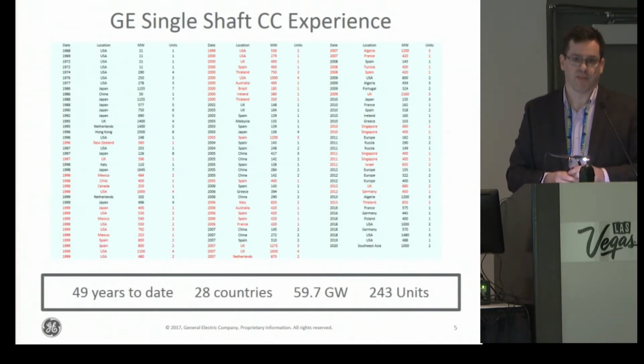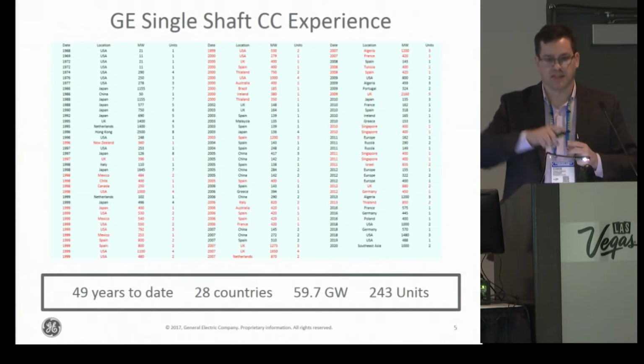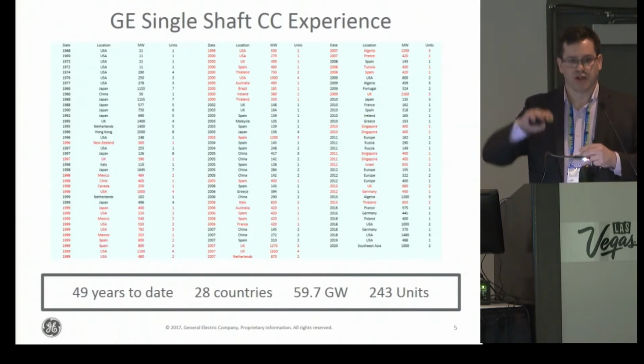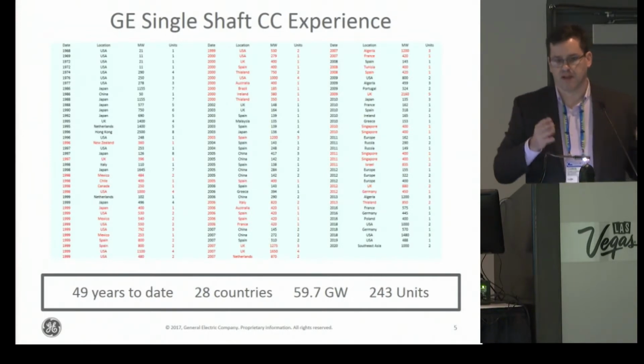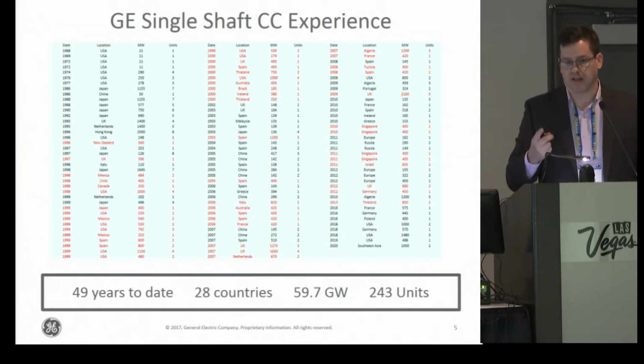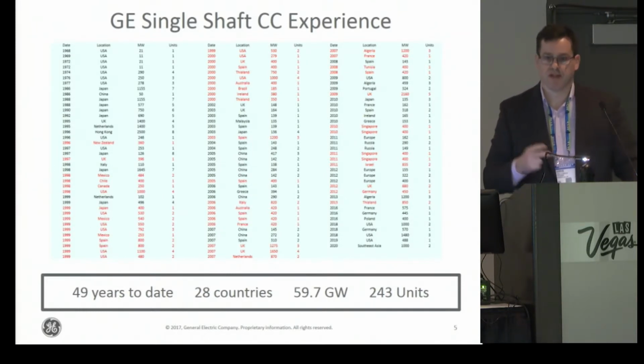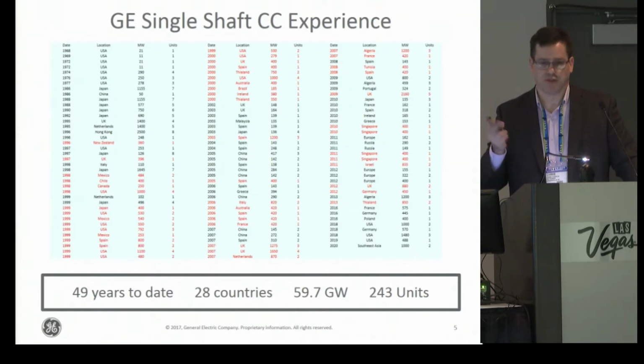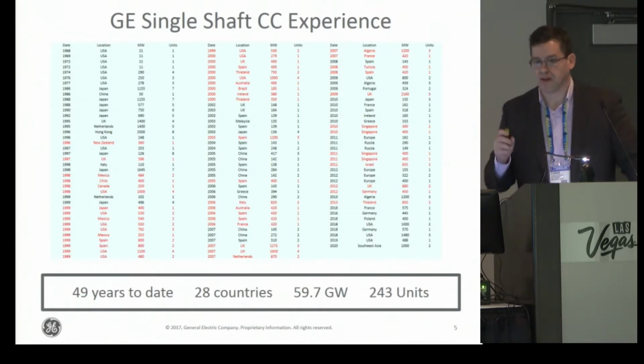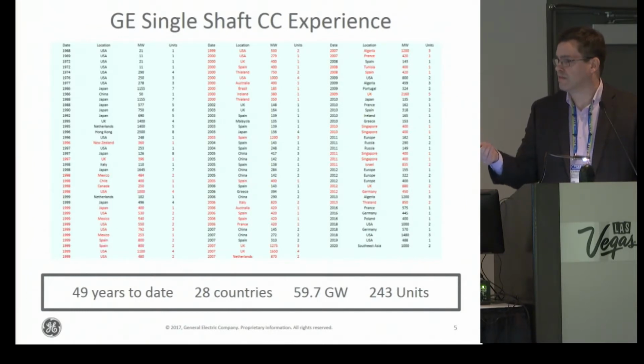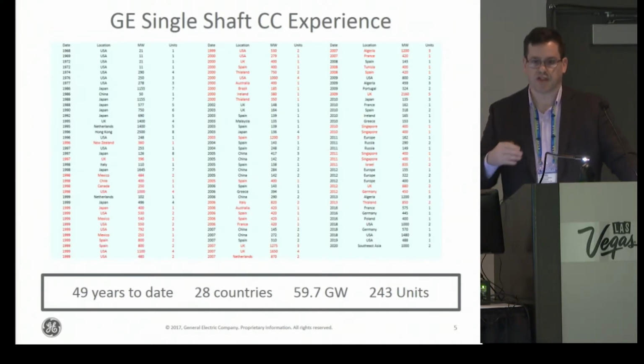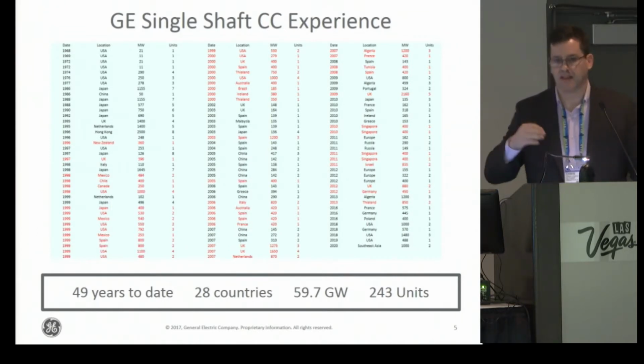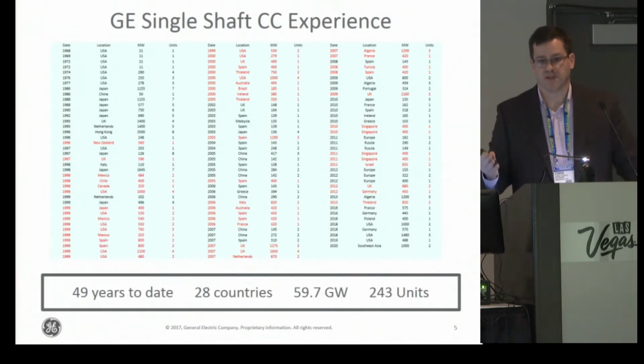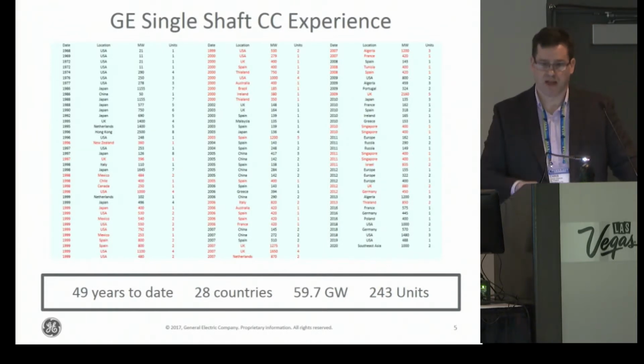That was one of the big reasons for it. Now, HA-class gas turbines have gotten so big that with the steam turbine there's not as much difference. You're on that flatter part of the curve, so to speak, of size versus efficiency. So now you can have a single gas turbine, or, say, two single shafts that are almost as efficient as a two-unit multi-shaft, maybe about 1/10 of a point. Whereas almost all of these units were in 50 Hertz, now you start seeing the later units being 60 Hertz, with single shaft being much more popular. It's still not leading the way, still not the highest percentage of units out there, but we're seeing many more now than we did, say, 15 years ago when the gas turbines were a lot smaller.